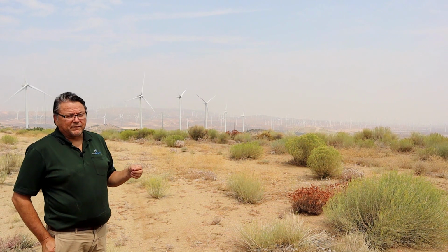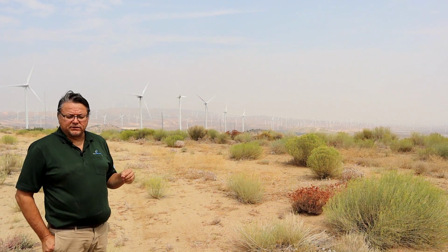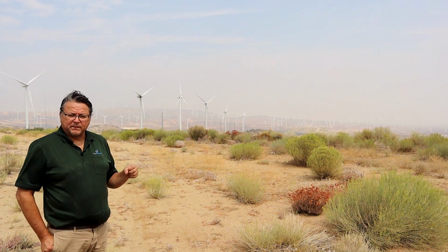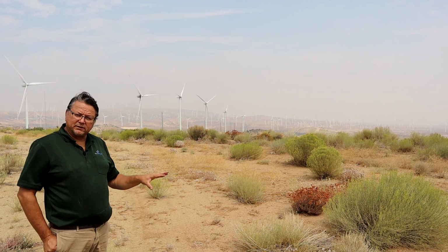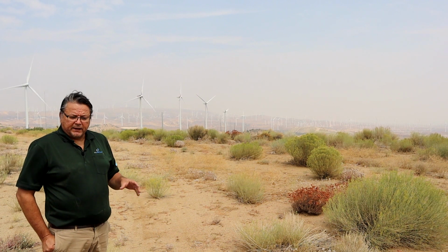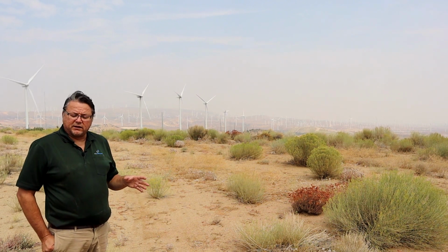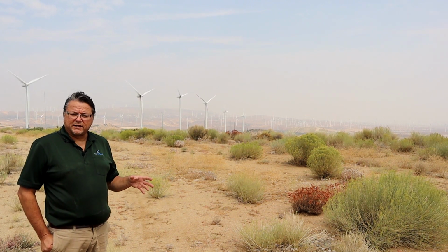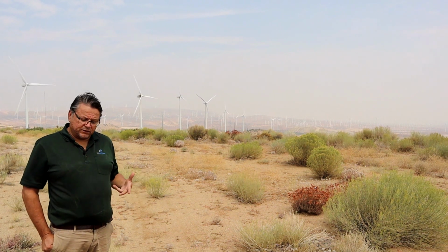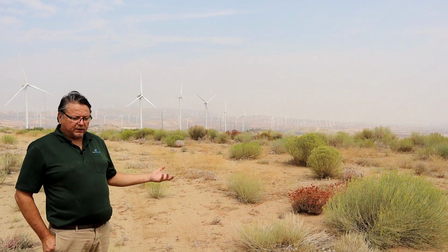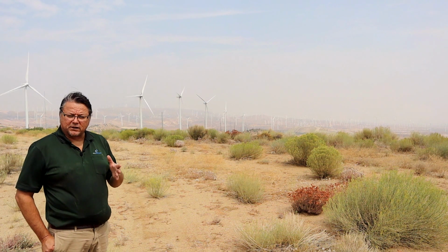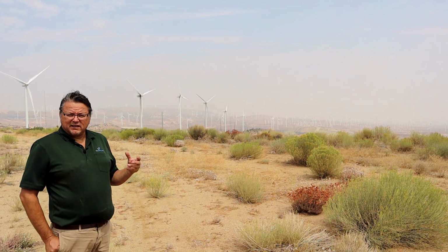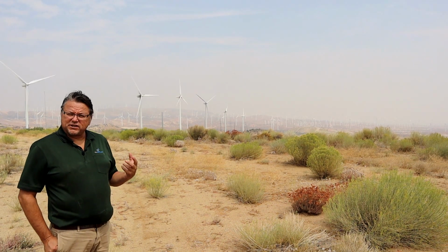What we have to do, and what the operators of the turbines have to do, is closely monitor the plant load and our generation from these turbines. As they approach that trip set point, if there's enough wind and our load's at the right point, we're going to start approaching the trip set point, and they can reduce the generation from these generators.